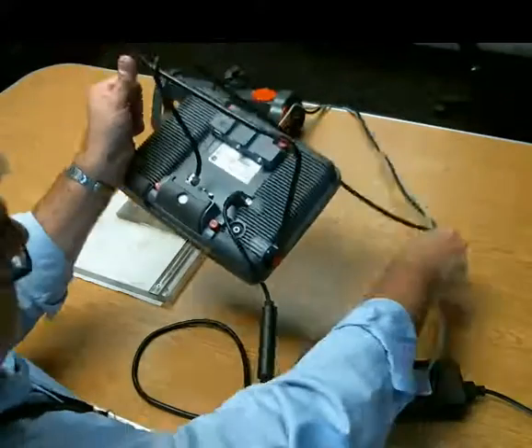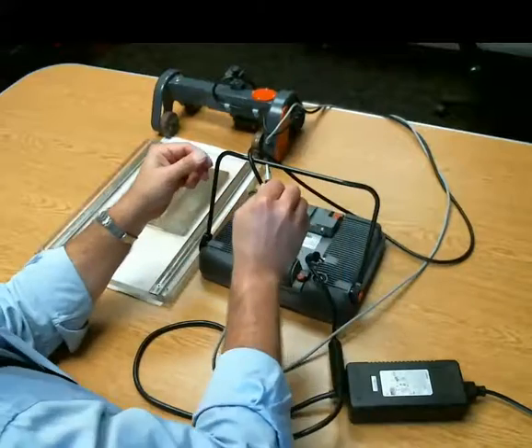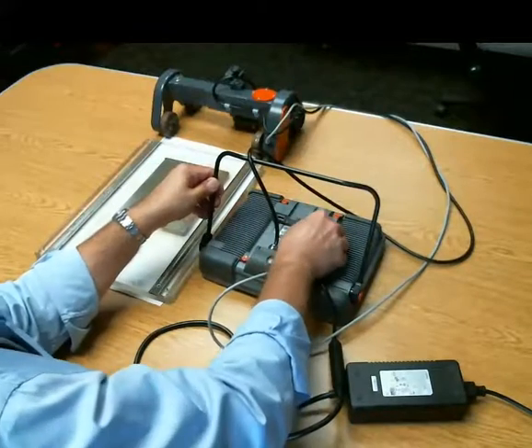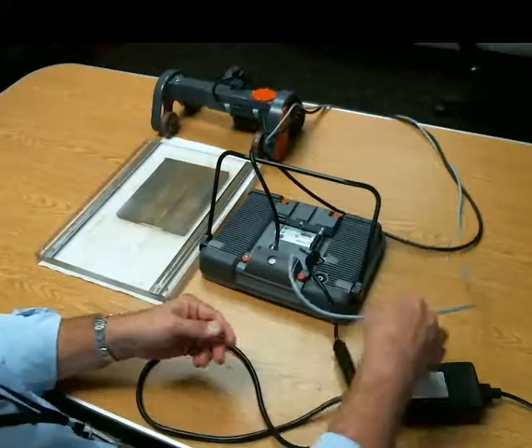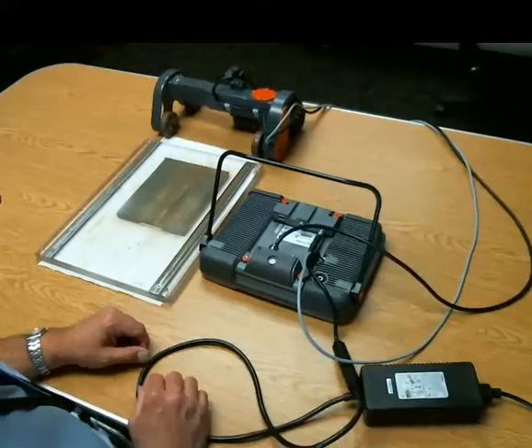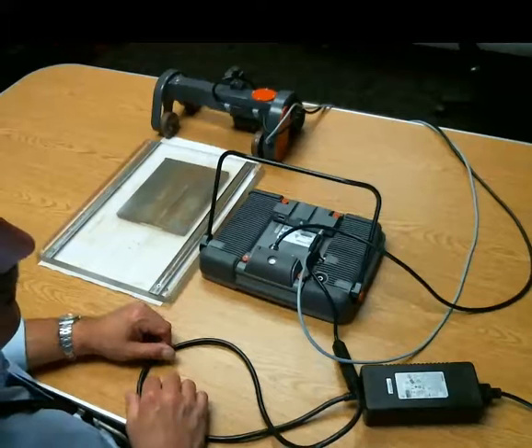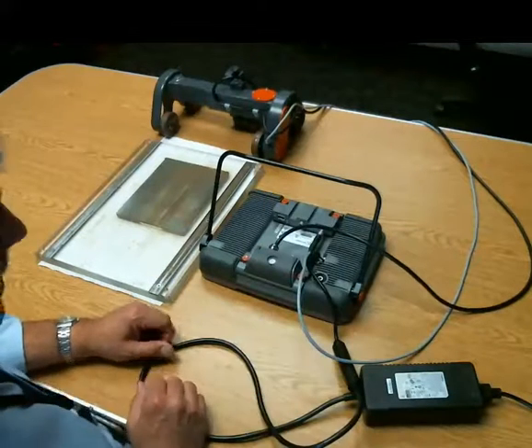If you accidentally plug into the Z connector with this, you won't hurt anything necessarily, but the instrument will turn off as soon as you move the encoder. So if you ever run into that, you put your system together, you've turned your instrument on, you're trying to do something, but every time you touch the encoder, the instrument turns off, most likely you plugged into the Z connector by mistake.